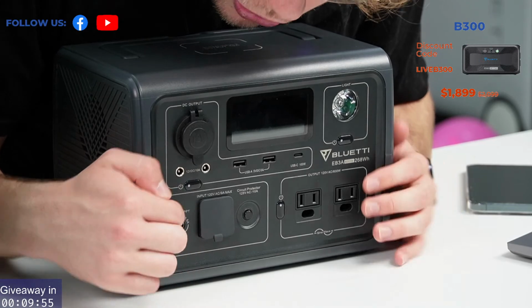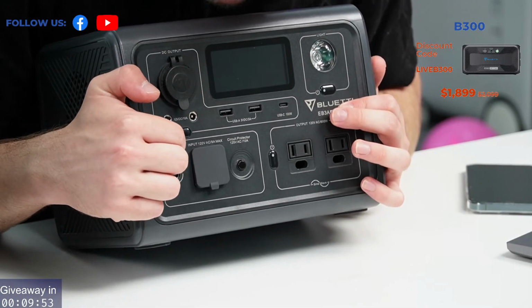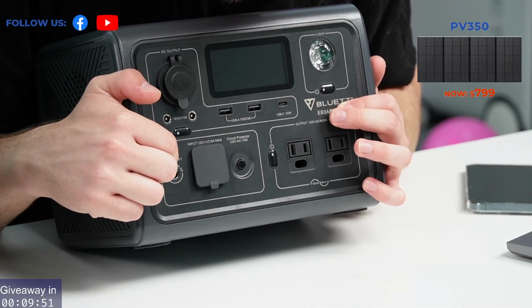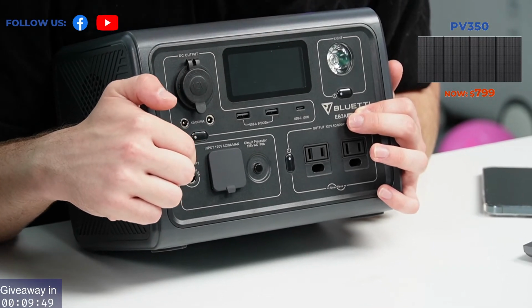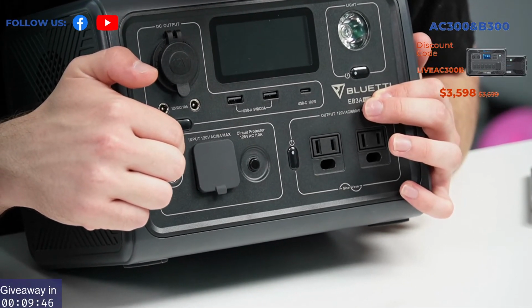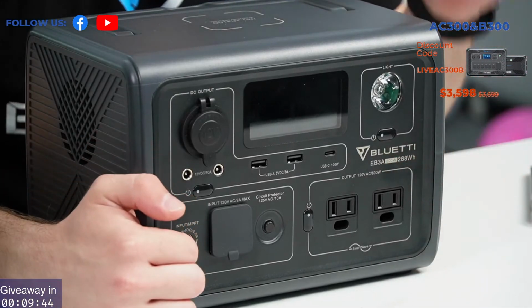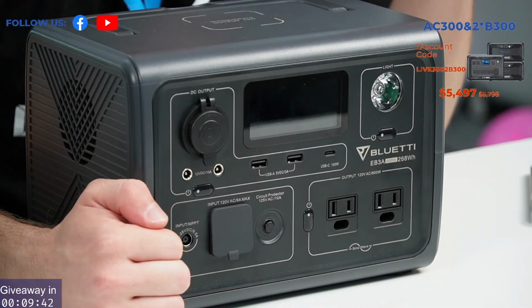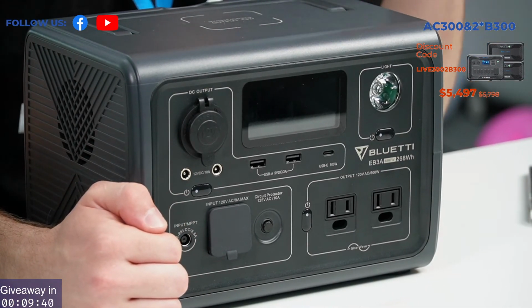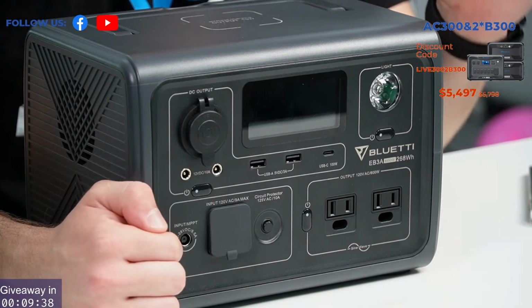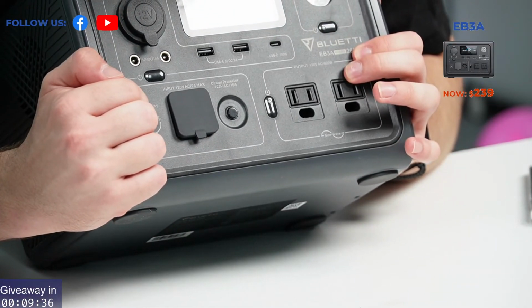We also have this MPPT input. This is the solar input, 12 to 28 volts DC open circuit voltage and 8.5 amps. So choose solar panels that do not exceed 8.5 amps max, with open circuit voltage in the range of 12 to 28 volts.